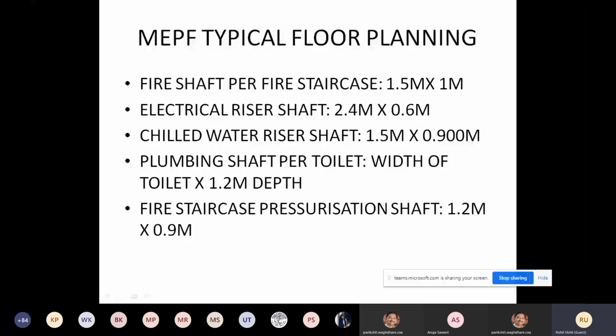And in case you have a fire staircase which is within the building and is not ventilated to the atmosphere, then you need a size of approximately 1.2 meters by 0.9 meters. I'll just delve a little more into this fire staircase and pressurization as we move on.